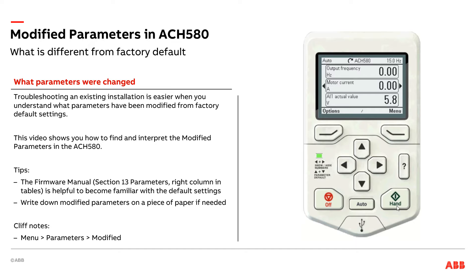Depending on the drive manufacturer, your preference, or your experience and training, you might call these change parameters. In the ACH580, they are called modified parameters. What these are, are parameters that are different than the factory default settings. This is a really good tool to use when you're walking up to a drive for the first time and you're going to be troubleshooting, or maybe finishing commissioning and you want to understand exactly how this drive is programmed. If you have an idea of what the factory default settings are, all you need to do is navigate over to modified parameters and get a really quick list that walks you through what is different. Let's go ahead and do that and take a look.